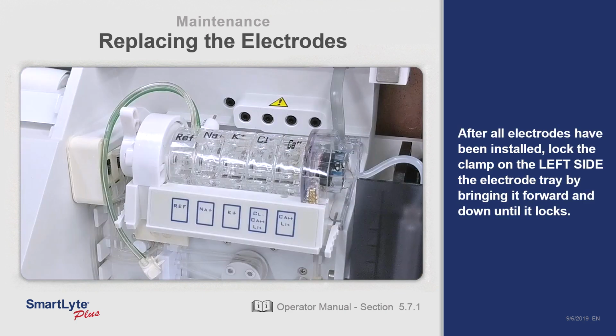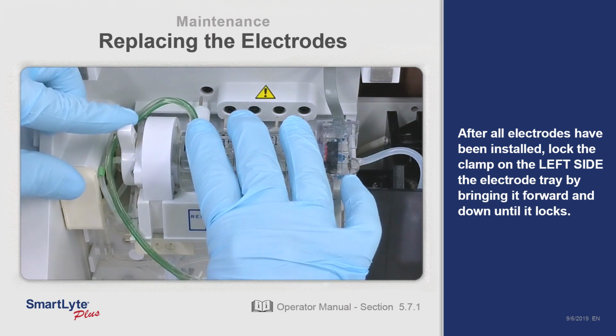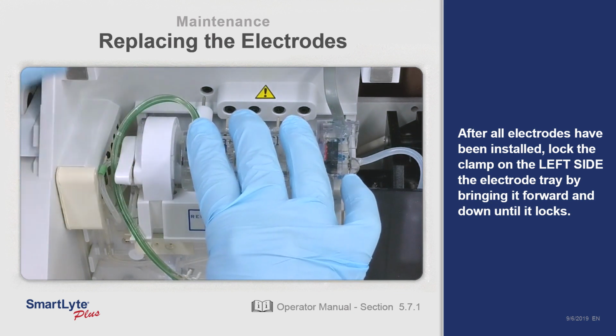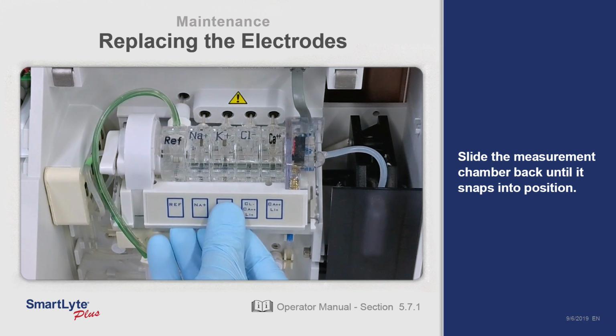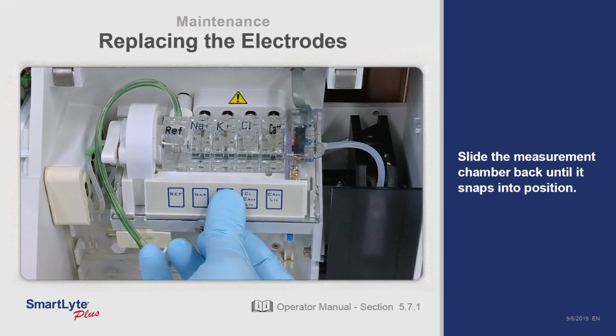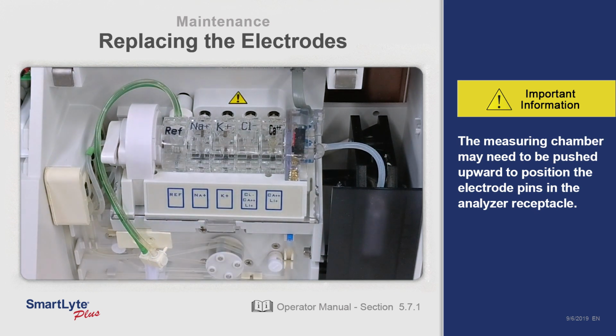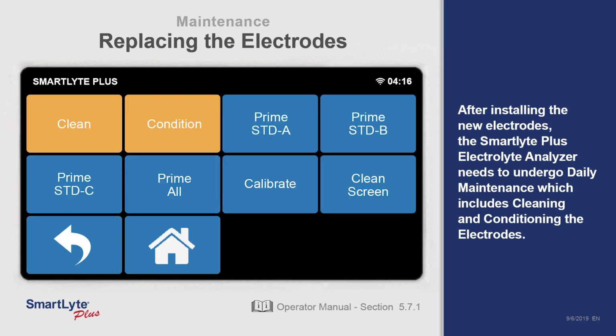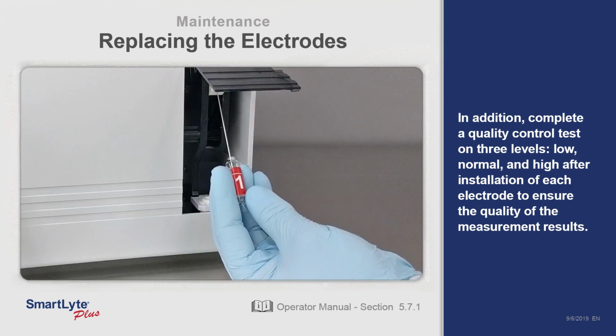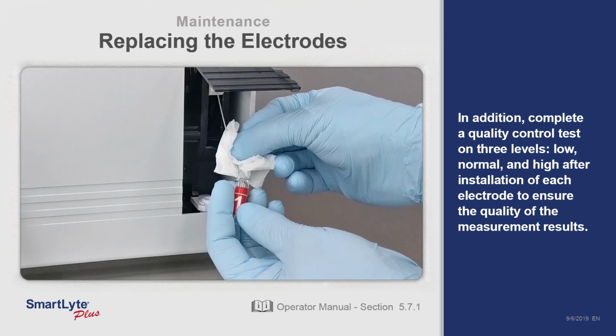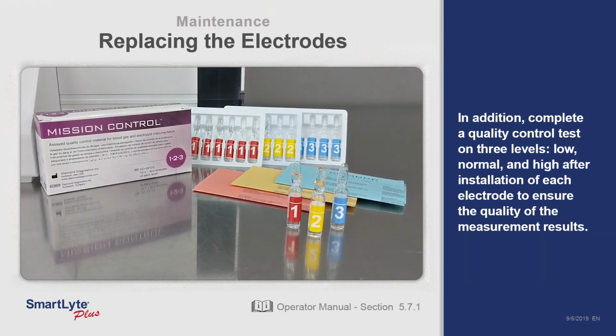After all electrodes have been installed, lock the clamp on the left electrode tray by bringing it forward and down until it locks. Then, slide the measuring chamber back into position. The measuring chamber may need to be pushed upward to position the electrode pins in the analyzer receptacle. After installing the new electrode, the SmartLyte Plus electrolyte analyzer needs to undergo daily maintenance, a calibration, and QC measurement to verify the performance of the electrode. In order to ensure the quality of the measurement results, complete a quality control test on 3 levels: low, normal, and high, after installation of each electrode exchange.